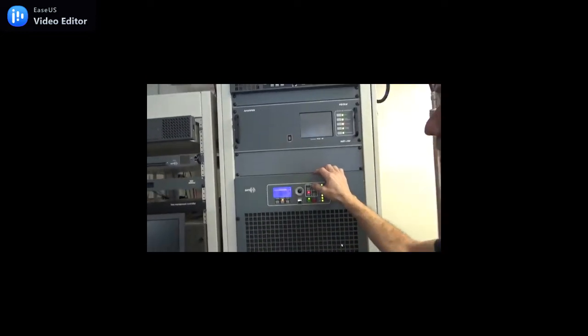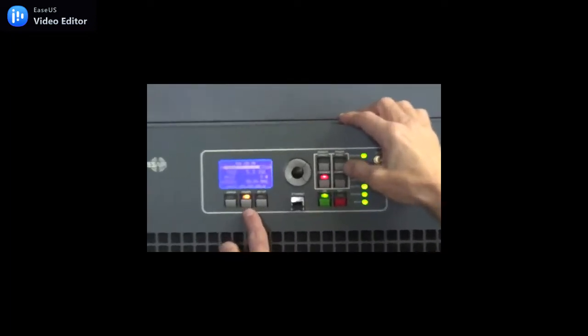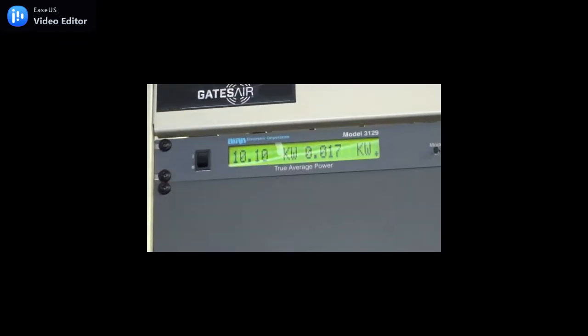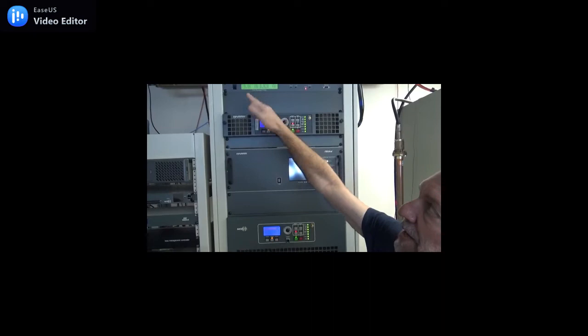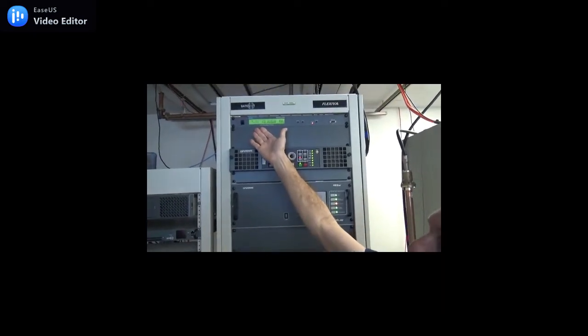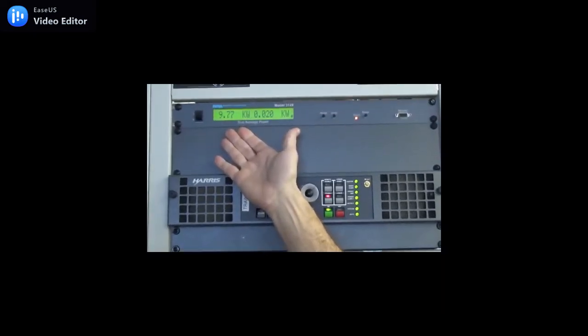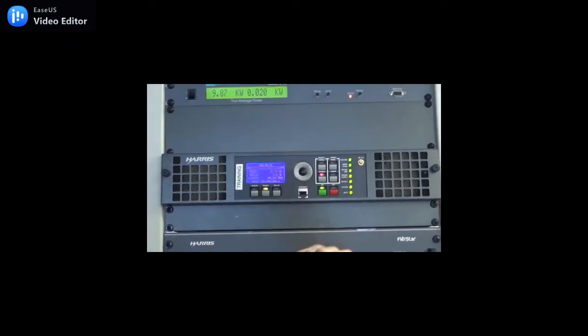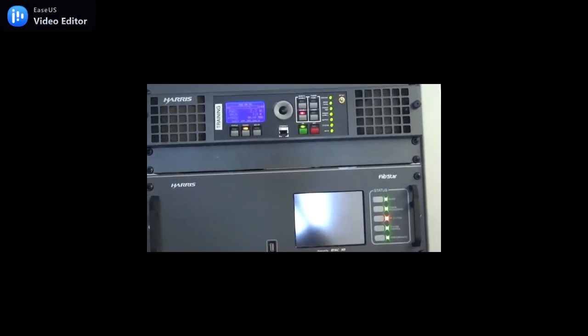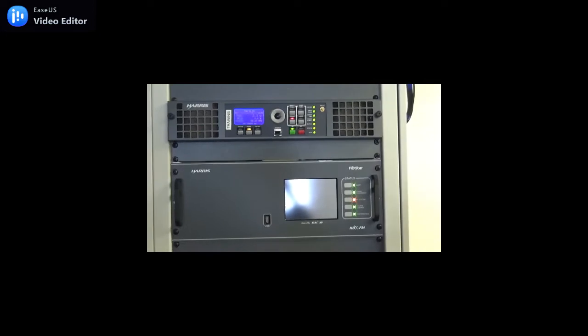So now your external meter and your front panel meter should match. Okay? In the procedure. So we're now calibrated. We have 9.9 kilowatts on our external meter. We have 9.9 on our front panel. So at this point, now we're ready to set the APC limit.